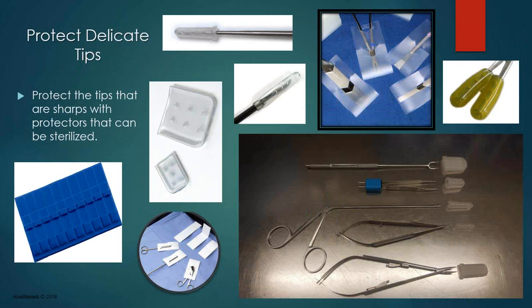Many times I go into facilities and open random peel packs, and before I can even open it, the tip protector has already fallen off. Or I can't get it off at all without using strong force. It's really important for aseptic technique in the OR that the tip protector is put on correctly, because it can contaminate the field, or I can injure myself as a scrub, which I've done before, when a skin hook couldn't come out of a vented tip protector.